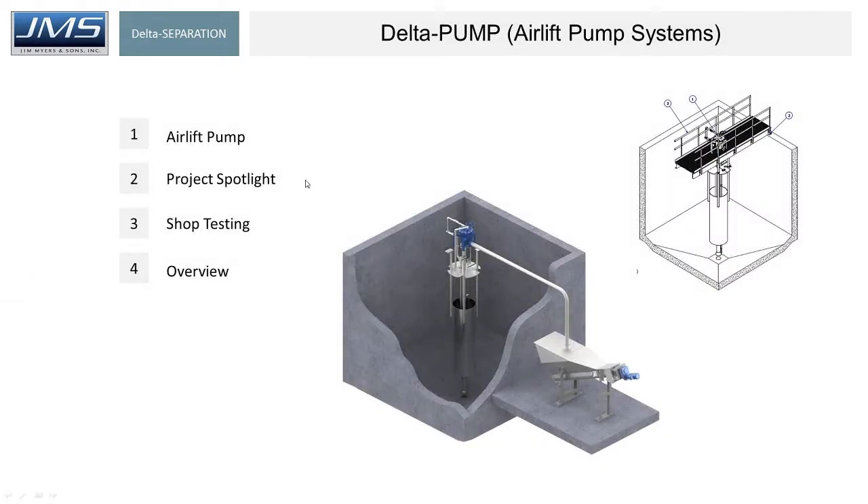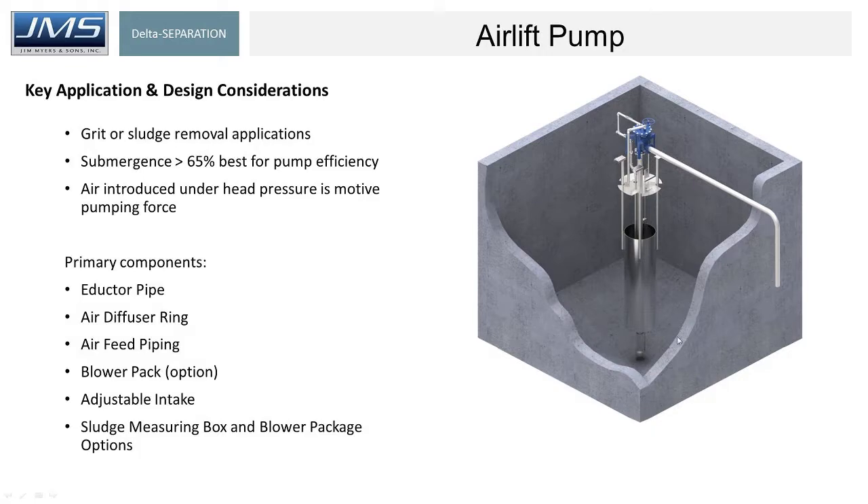Further in grit removal separation is the airlift pump system — been around since the beginning of time. A very simple process. You can see a depiction here where the floor of the basin is sloped such that grit accumulates. A blower provides high-volume air — not high-pressure, but high-volume. Air is injected near the bottom into the eductor, an airlift pump. As the air rises, the grit rises with it and comes out the discharge pipe. They can be used for grit or sludge removal applications, but most often we see them for grit.